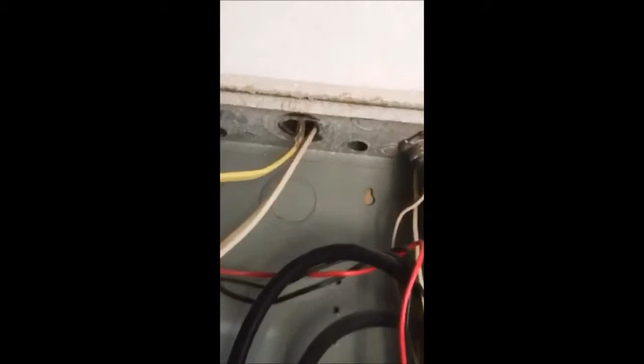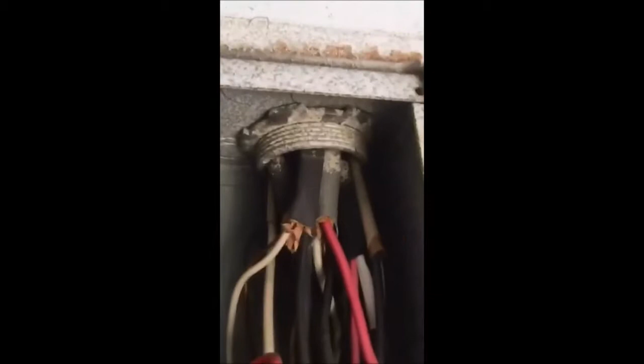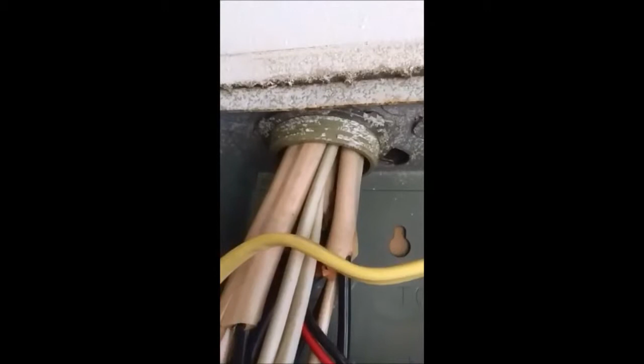Now, here are some of the things that we find typically on our inspections. First one I wanted to look at is we have no Romex connector or bushing around these wires coming into the main electrical panel. They should have a Romex style connector or a bushing protecting the wires coming into the panel, like you see here.